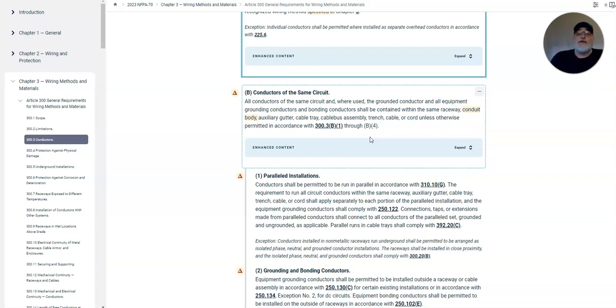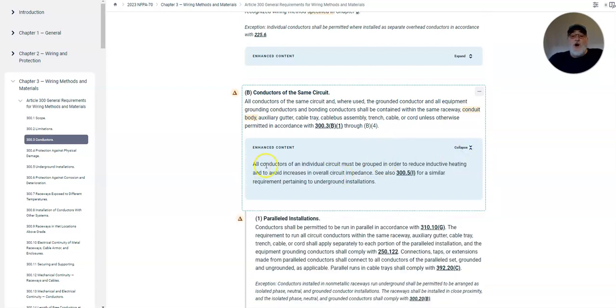They cannot be separated. You can't have your hots in one conduit and your neutrals and ground in another conduit, specifically because it will cause very bad problems in the electrical system. Okay, let's do this. All conductors of an individual circuit must be grouped in order to reduce inductive heating and to avoid increases in overall circuit impedance. 300.5 has a similar requirement pertaining to underground installations. That's what you get, because you get inductive heating and you have to avoid the impedance.